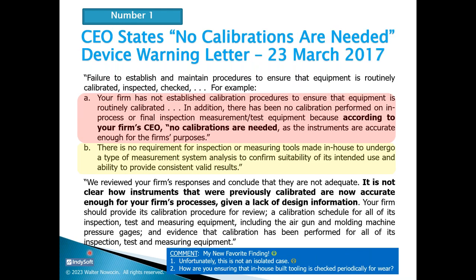Number one, drum roll. The CEO states no calibrations are needed. Your firm has not established calibration procedures to ensure that equipment is routinely calibrated. In addition, there has been no calibration performed on in-process or final inspection equipment because, according to your firm's CEO, no calibrations are needed as the instruments are accurate enough for the firm's purposes. Oh my goodness, this is my new favorite finding.